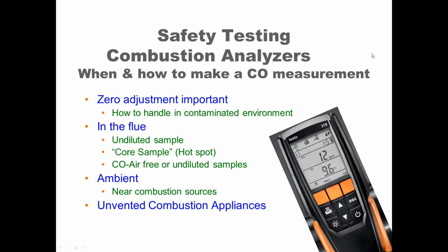So let's cover now combustion safety testing and using the carbon monoxide function of your combustion analyzer. With all analyzers, it's very important to get the zero adjustment set. You want to make sure that you follow the manufacturer's recommendation to start the analyzer, usually with the probe in an area that you believe to be free of any carbon monoxide.